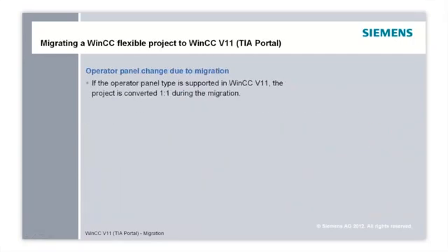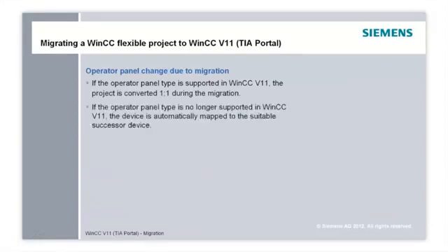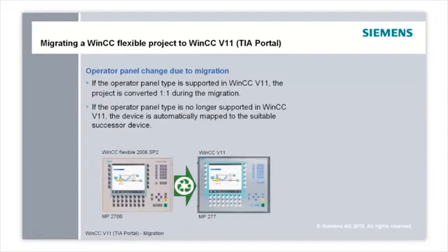What happens to an operator panel during migration? If the operator panel type in the WinCC Flexible project is also supported in WinCC version 11, the project is converted one-to-one during the migration. If the type of the operator panel to be migrated is no longer supported in WinCC version 11, the device is automatically mapped to the suitable successor device. In the displayed example, the MP270B is migrated to MP277K.